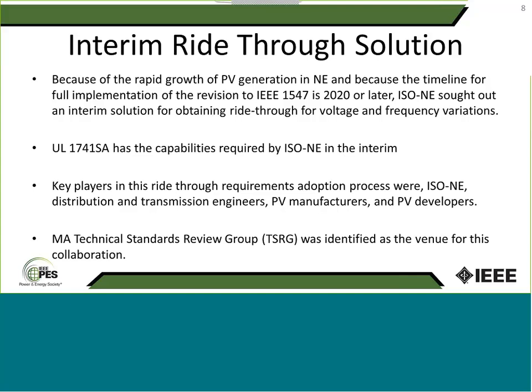Plus the NRTLs need another 5 to 6 months to revise their test regimens to adopt the new 1547.1. So the point is, ISO New England is concerned about that process and says, with the existing solar growth in New England, we really cannot wait till 2020 or later to adopt ride-through. They're already starting to see that when they have faults on 345 kV lines, they're seeing some potential trips for some DERs with existing 1547 settings.